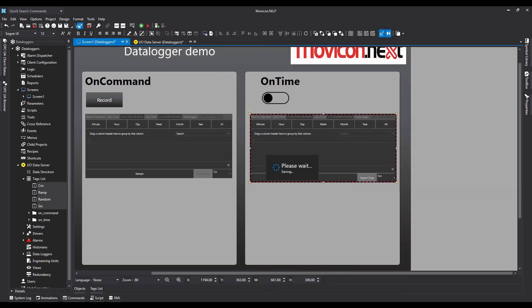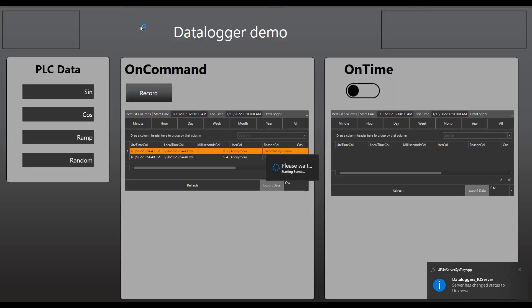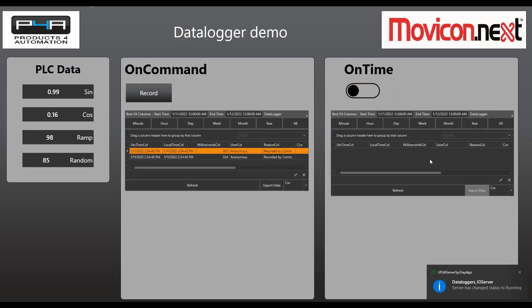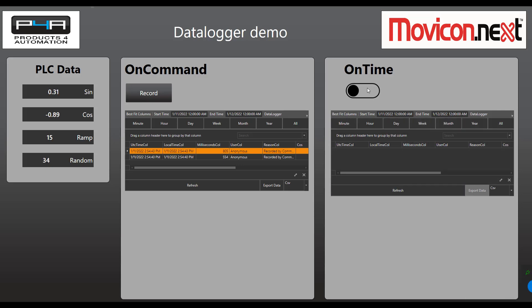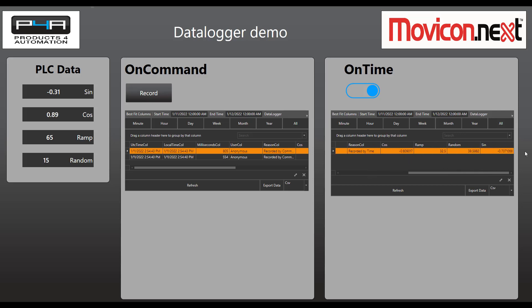We'll then save all and let's start it. If we hit Refresh now, we've got nothing coming through, even after five seconds. When we enable and wait for five seconds, we can see that the tags have been recorded - By Time as the recorded reason - and the values are there. We can see every five seconds.